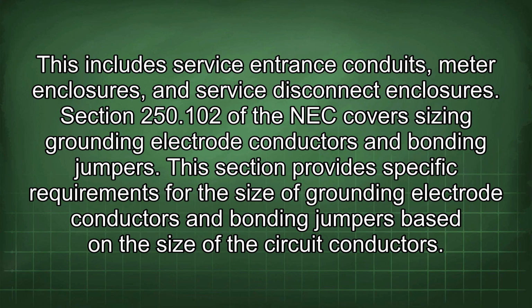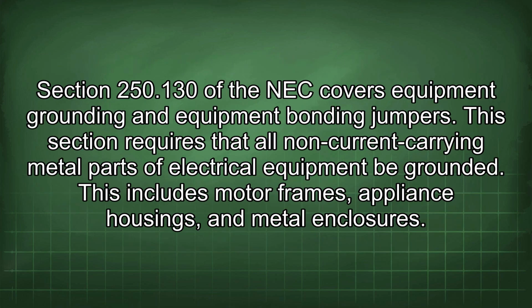Section 250.102 of the NEC covers sizing grounding electrode conductors and bonding jumpers. This section provides specific requirements for the size of grounding electrode conductors and bonding jumpers based on the size of the circuit conductors. Section 250.130 of the NEC covers equipment grounding and equipment bonding jumpers. This section requires that all non-current carrying metal parts of electrical equipment be grounded. This includes motor frames, appliance housings, and metal enclosures.